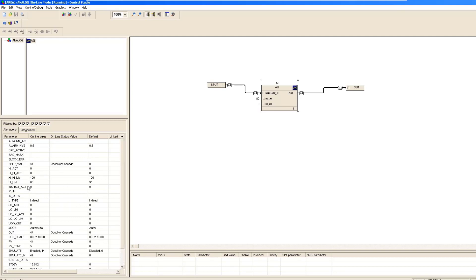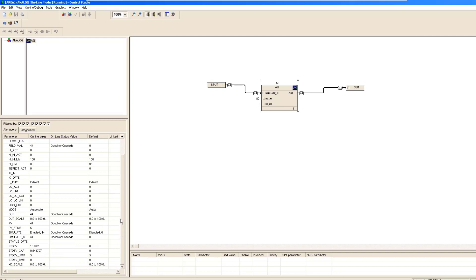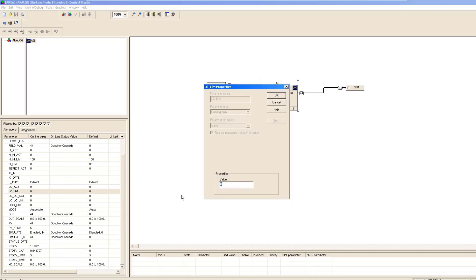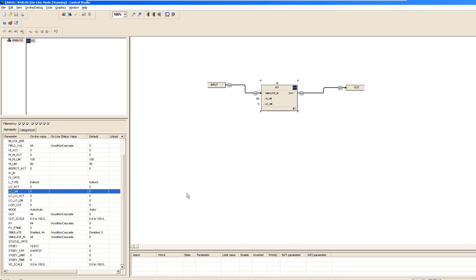Here we get to the Low Limit. If I change it to, for instance, 10, you will see that our Low Limit changes to 10 here. Now if our value gets lower than 10, it should give us a Low Alarm, and if our value exceeds more than 80, it should give us a High Alarm.